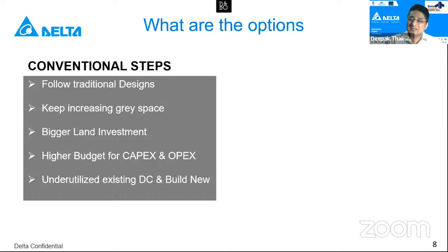So what does that mean? That means you have to have a much bigger gray space area dedicated to provide the power to your white space, which is the rack space. So either you maintain this, or you keep increasing the gray space. That means you keep increasing your retail space footprint by acquiring larger land bank and bigger land investments, which is a huge cost itself, and then a higher budget for CapEx and OpEx because you are following traditional methodology, which was successful up to 10 megawatts, that is the 2N architectures and all those.